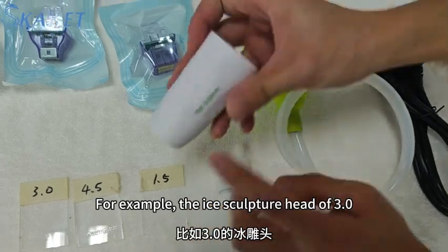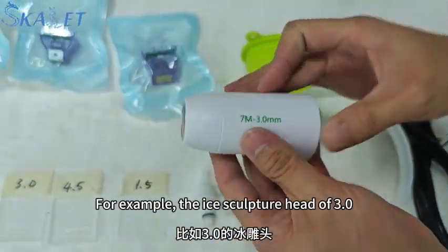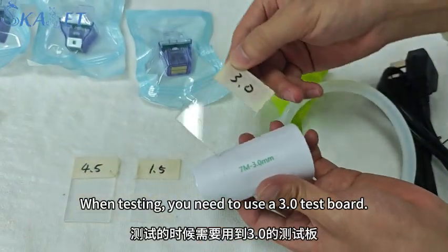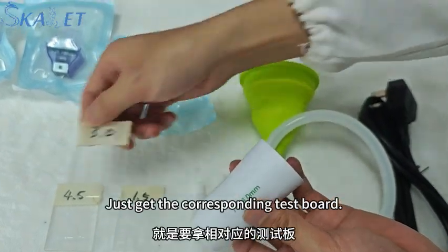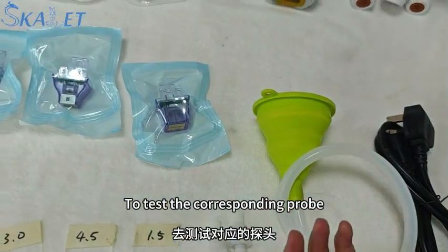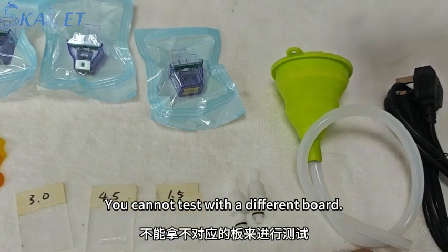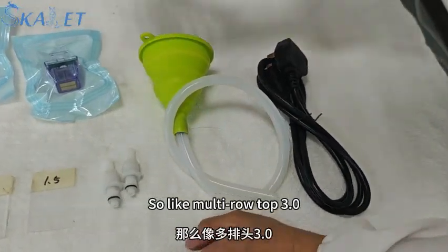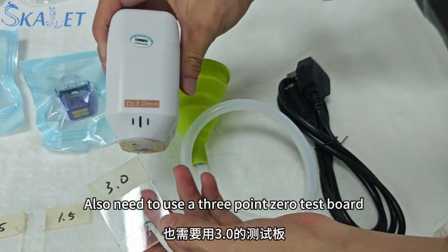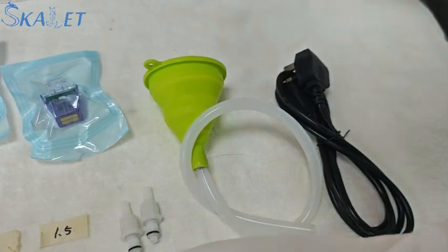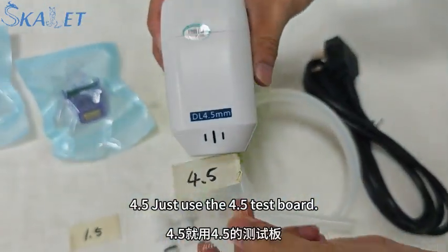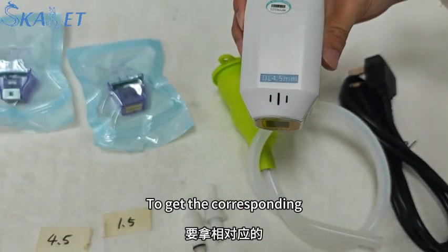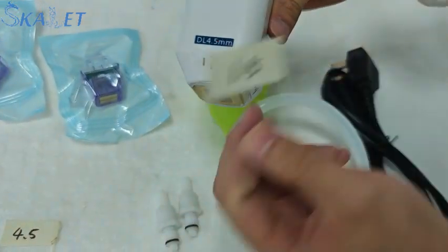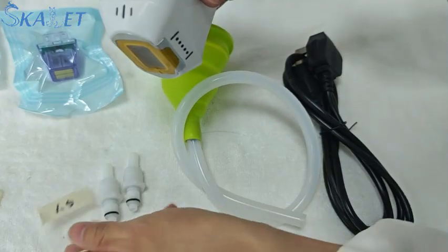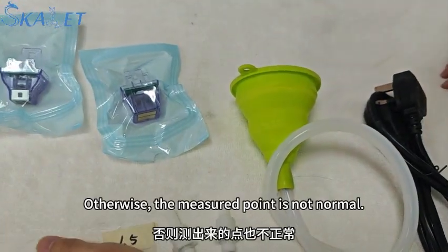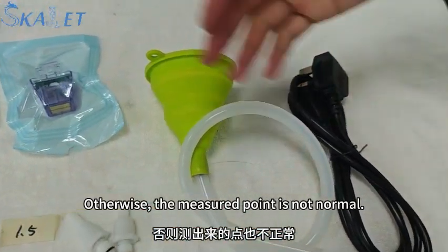For example, the ice sculpture head of 3.0. When testing, you need to use a 3.0 test board. Just get the corresponding test board to test the corresponding probe; you cannot test with a different board. So like multi-row top 3.0, also need to use a 3.0 test board. 4.5, just use the 4.5 test board to get the corresponding. Otherwise, the measured point is not normal.